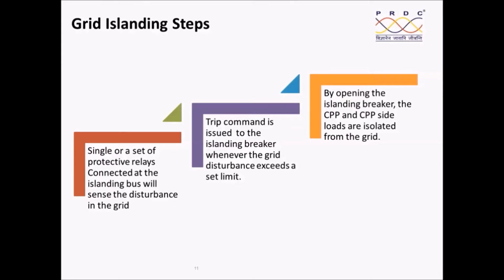Therefore, in the various grid islanding steps, a single relay or a set of protective relays connected at the islanding bus will sense the disturbance in the grid. What it means is, there will be one or two relays. It can be one simple grid islanding relay, or there can be a set of relays which are going to identify what the disturbance in the grid is. Once we identify the type of the disturbance in the grid, you'll be able to find out how best to island. Then we need to give the trip command to the islanding breaker whenever the grid disturbance exceeds a set limit.